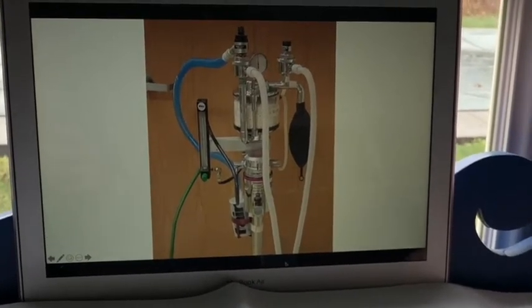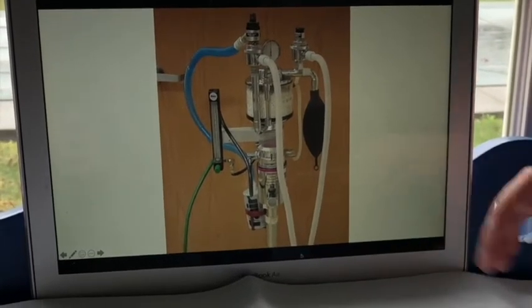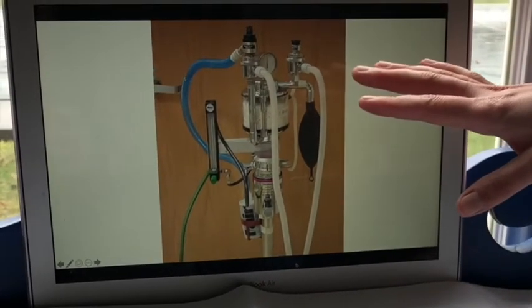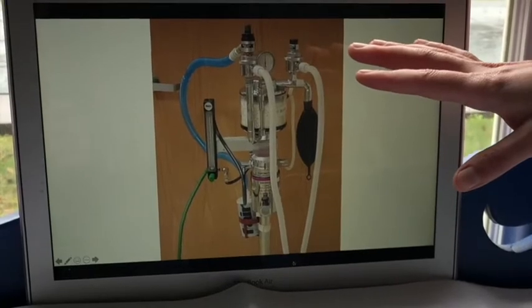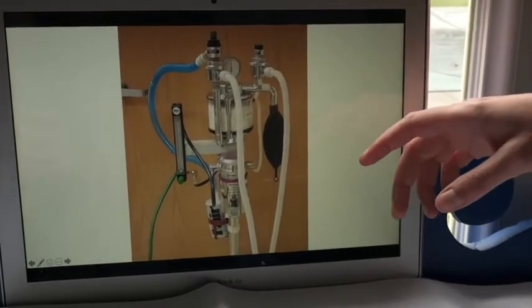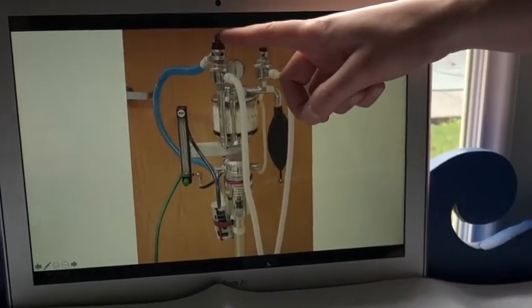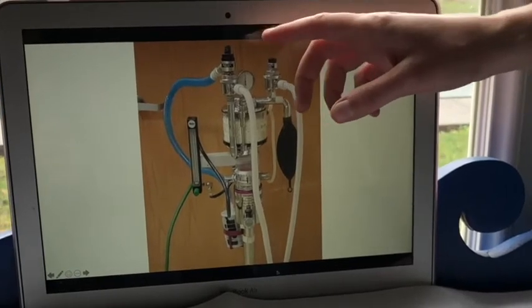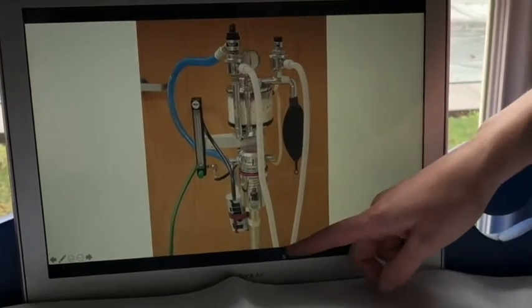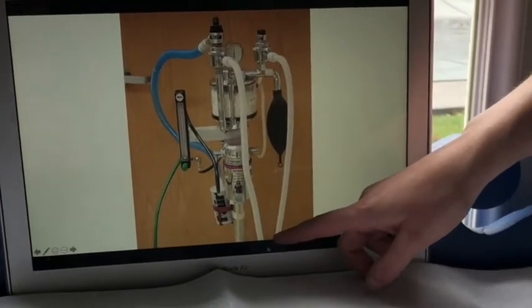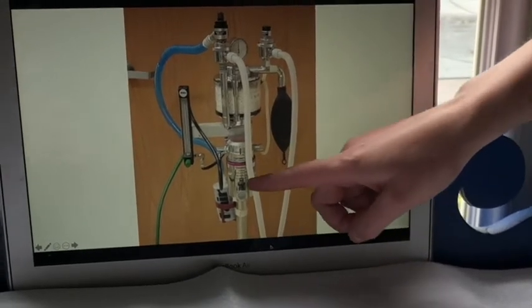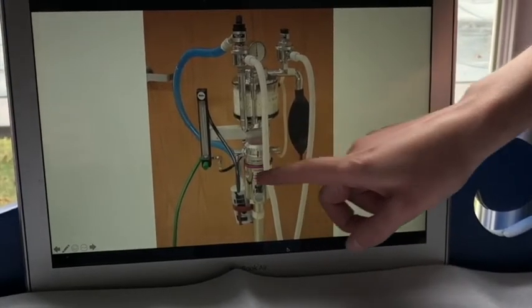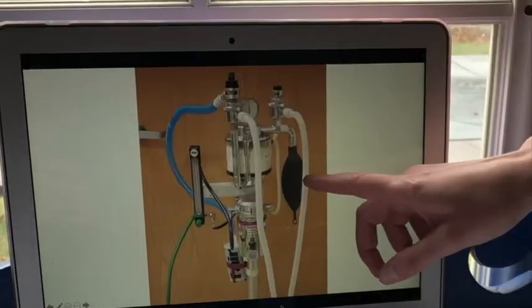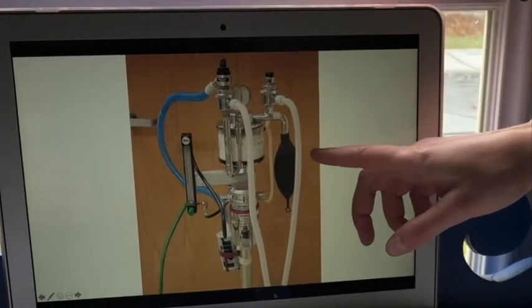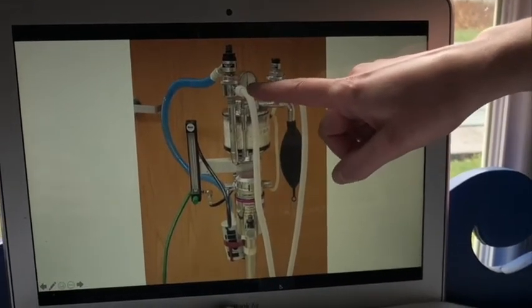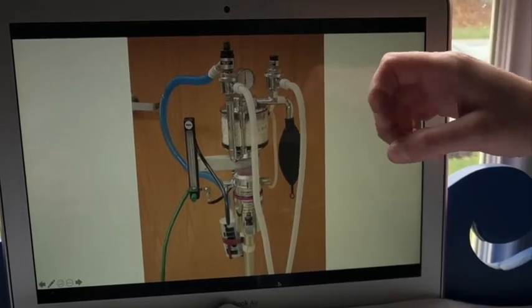well. And then once that's all done, checking out everything's all put together properly, we can do our leak test. So how we do that is we're going to close our pop-off valve, and then we're going to occlude the patient end of our Y piece here, and then use the oxygen flush valve to flood the system with oxygen until the pressure manometer, which is this little thing, reads 30 centimeters of water.